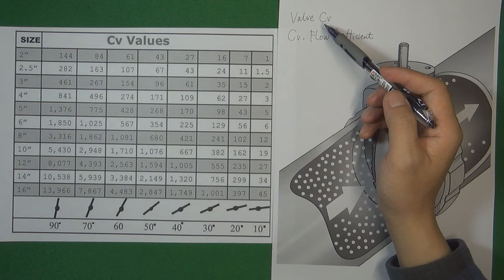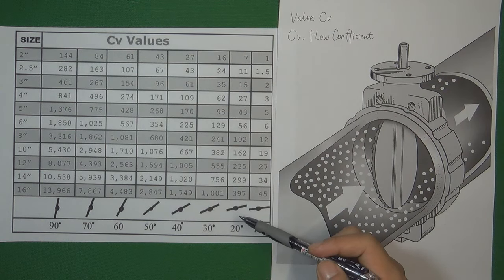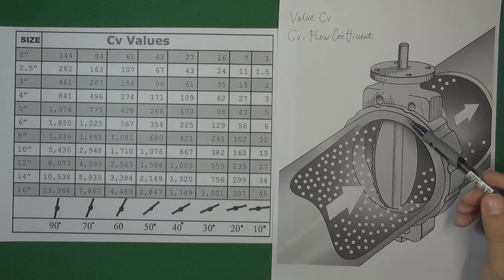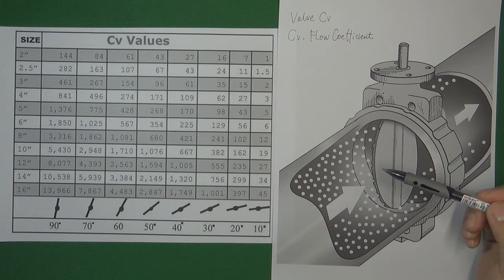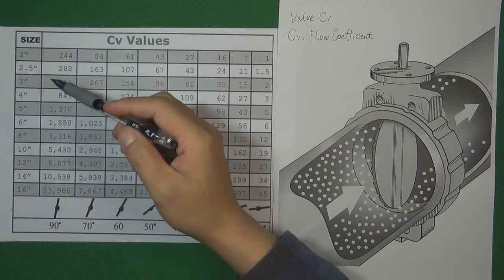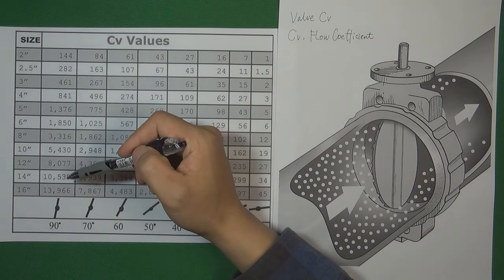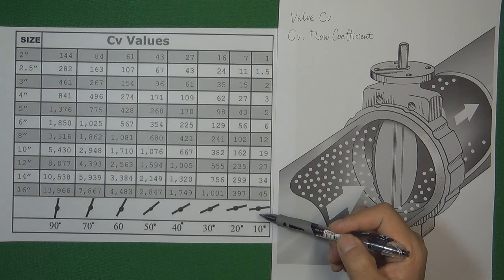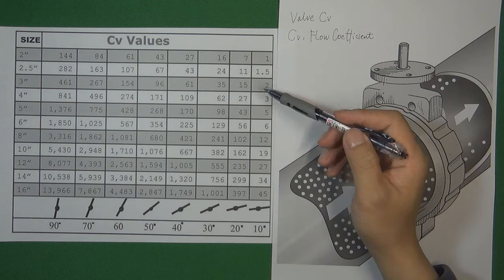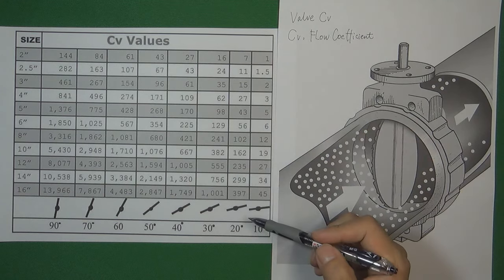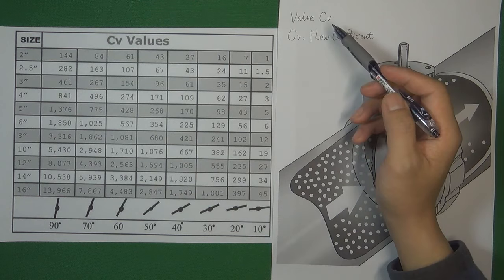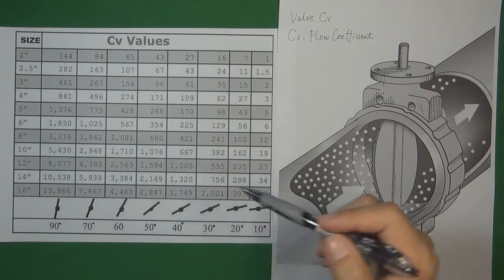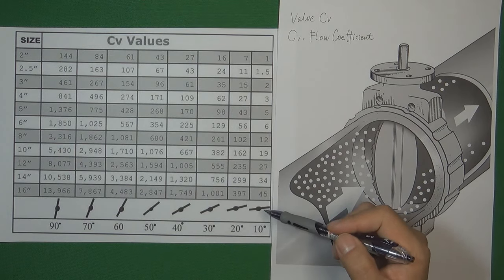Another thing is the position or the angle of the valve trim. Just like this butterfly valve — if the valve disc is fully opened at 90 degrees, the valve will have very high CV. But if the valve is close to 10 degrees, the valve will have very low CV. So valve CV is related to two things: one is the valve size, and another is the position or the angle of the valve trim.